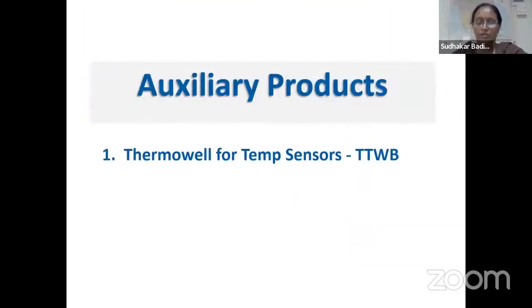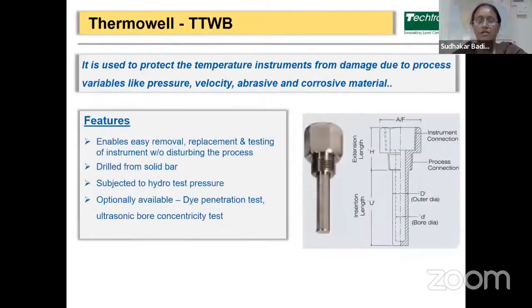This is the auxiliary product, that is the thermowell for temperature sensors. It is used to protect the temperature instruments from damage due to process variables like pressure, velocity, abrasive or corrosive materials. It enables easy removal, replacement and testing of the instrument without disturbing the process. It is drilled from solid bar, and at our factory, it is subjected to hydro test pressures, and they are available optionally. Various tests are available, such as dye penetration test and ultrasonic bore concentricity test.